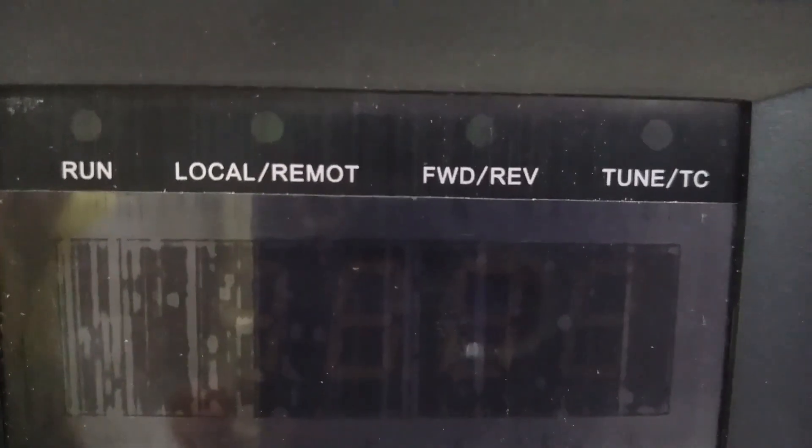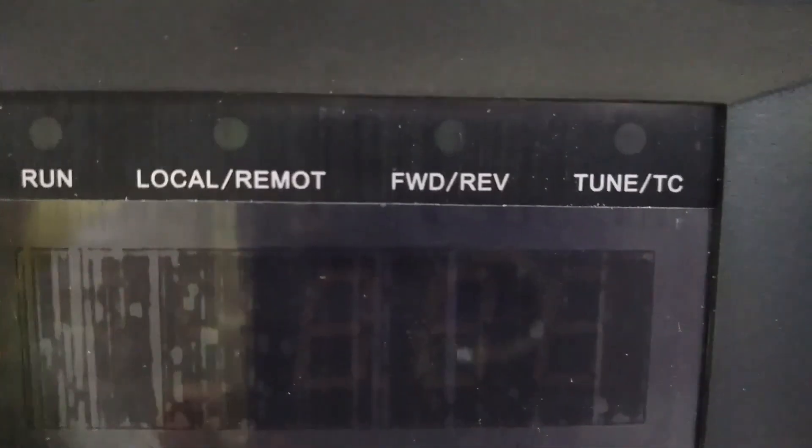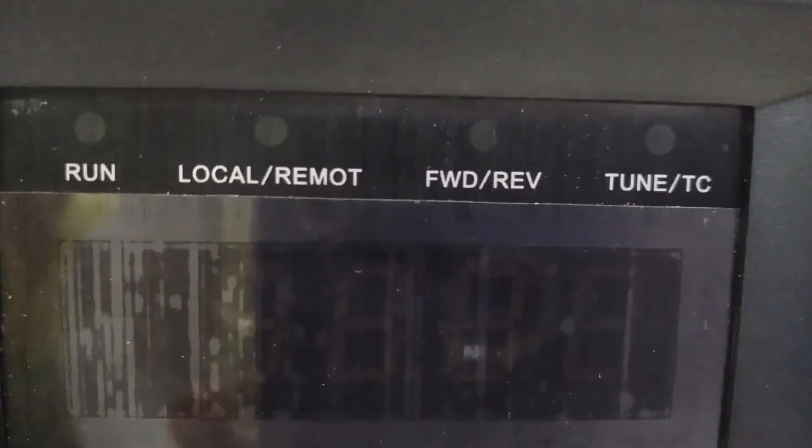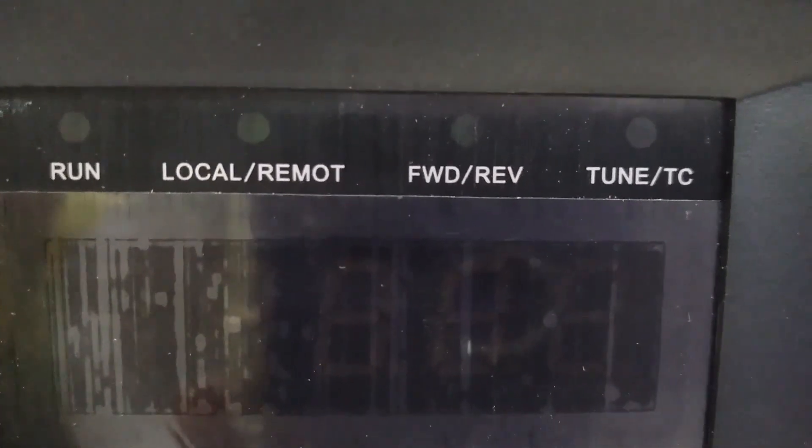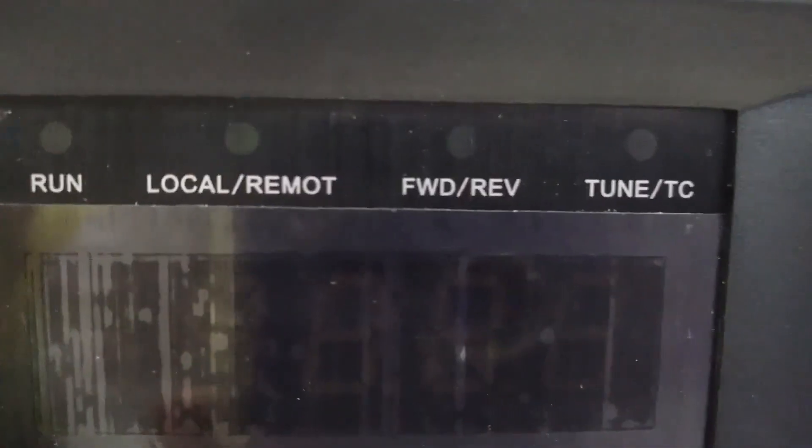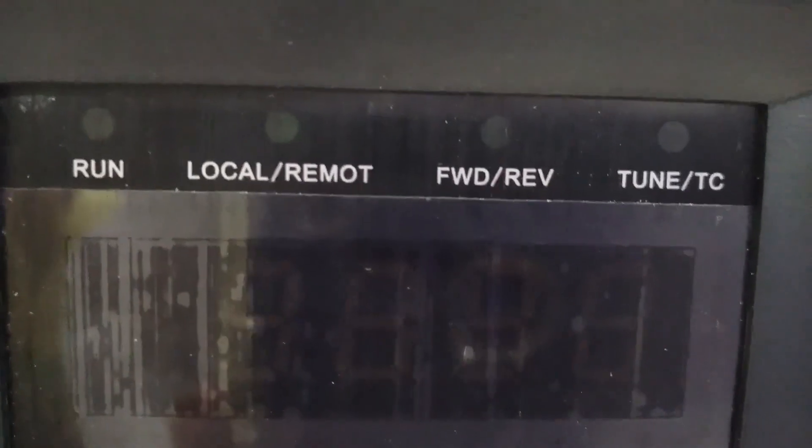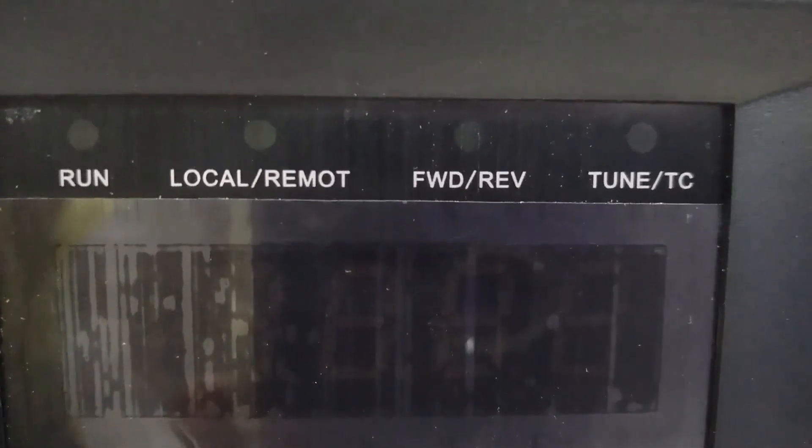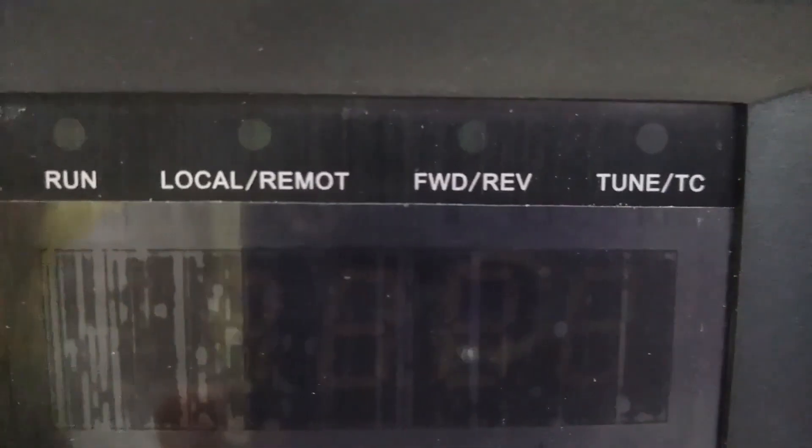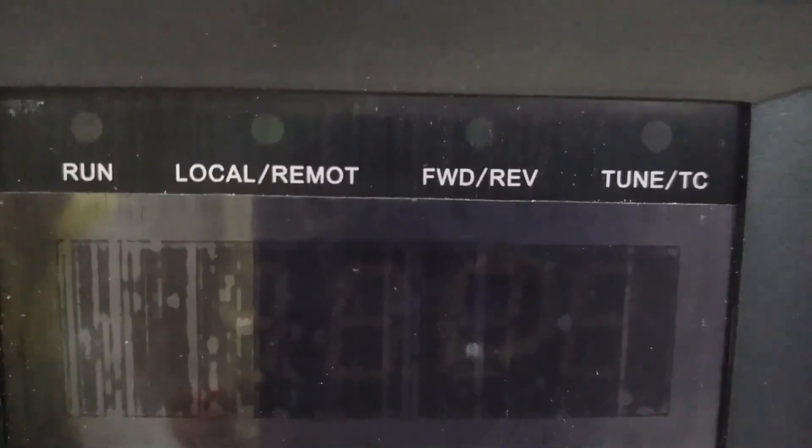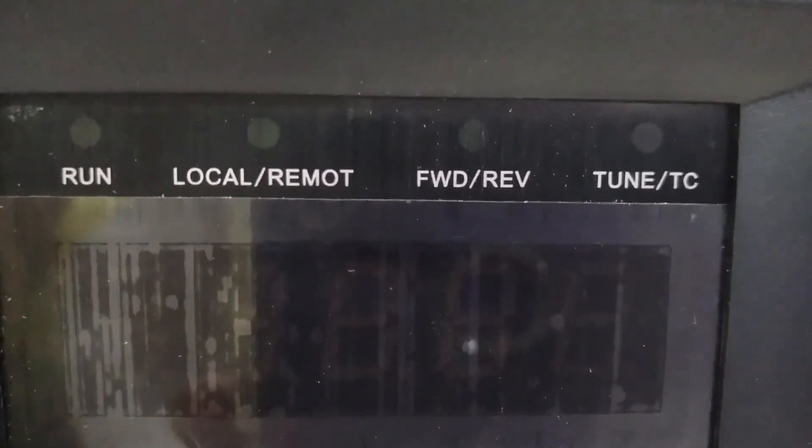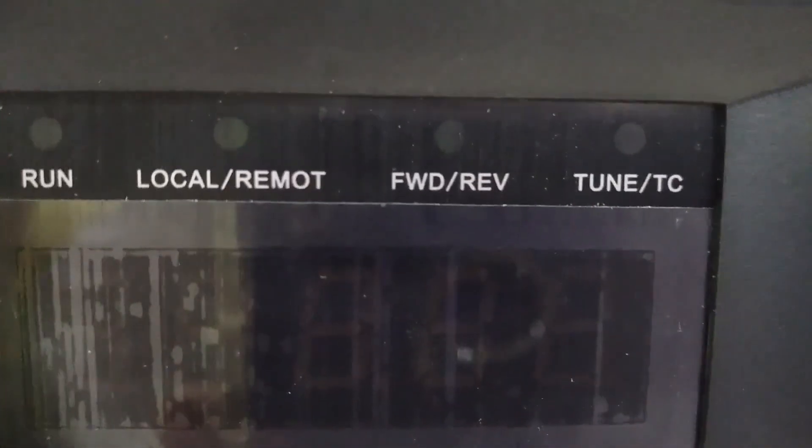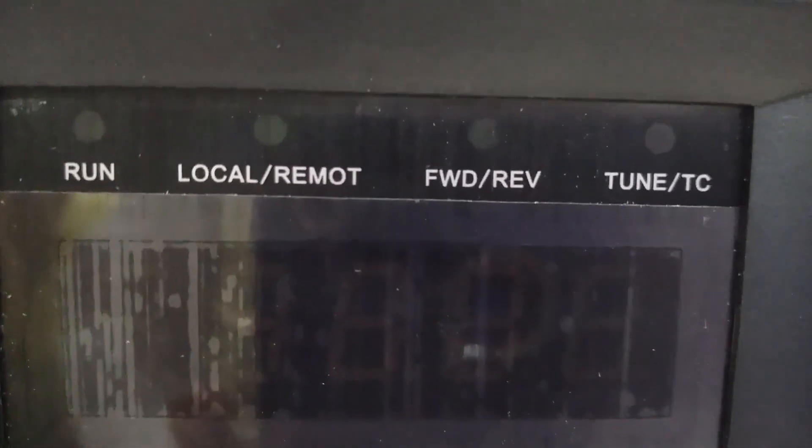If local/remote LED is on, then VFD will be operated from control terminals. If this LED blinks, it means the VFD is controlled from the communication port. Next we have forward/reverse LED. If this LED is off, the motor rotates in forward direction. If the LED is on, the motor rotates in reverse direction.